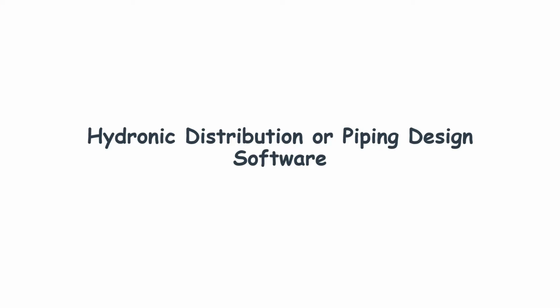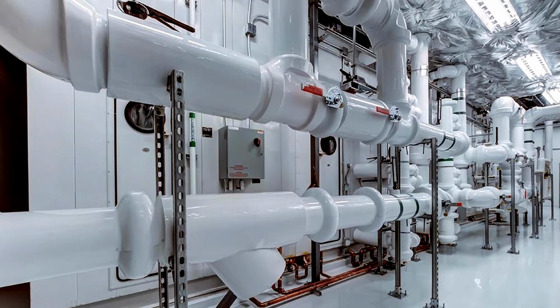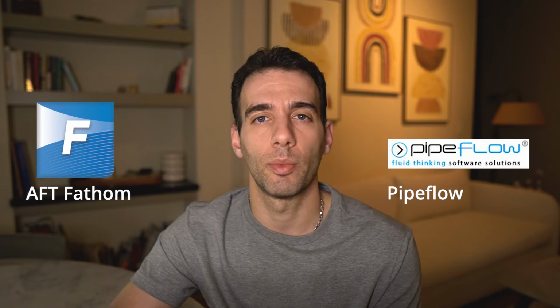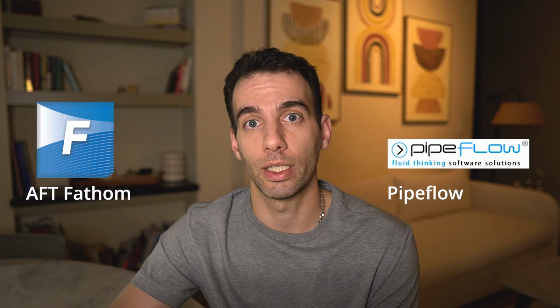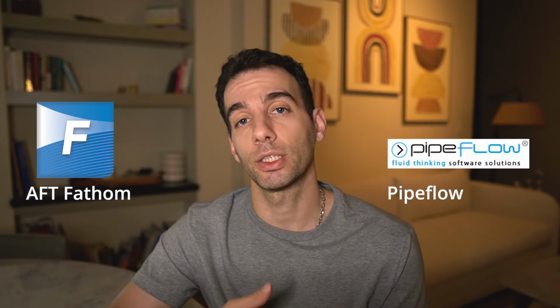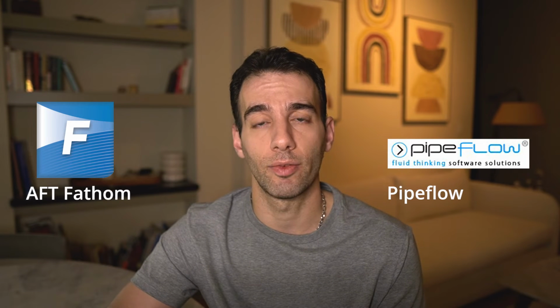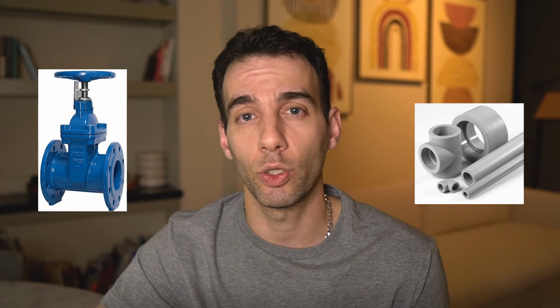Just like air distribution system design, piping design or hydronic system design is a very frequent task in HVAC engineering. AFT Fathom and Pipeflow are two of the most commonly used software for piping design in HVAC engineering. I personally work with these two software and they have every feature that you need for a complete piping system design. With these two software, you can model a piping system with all of its components such as valves, fittings, and really any equipment or component that you see in piping systems. Once you model all of that, you can calculate pressure drop in the entire system and size the right pump for your application.